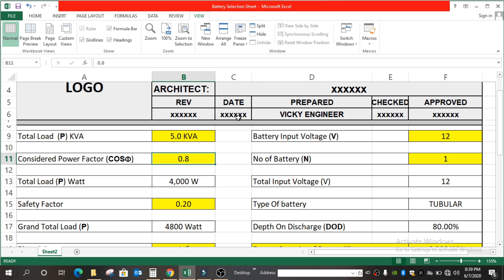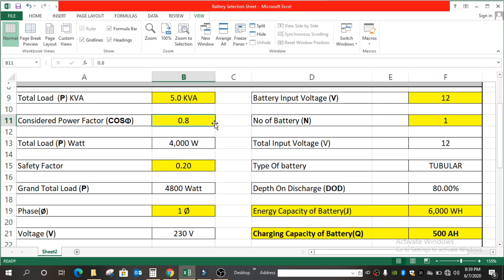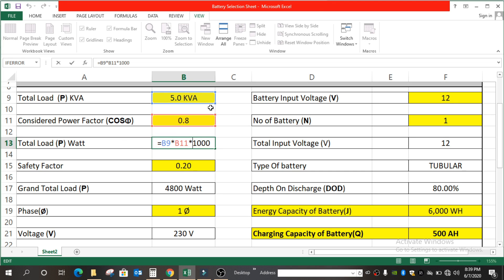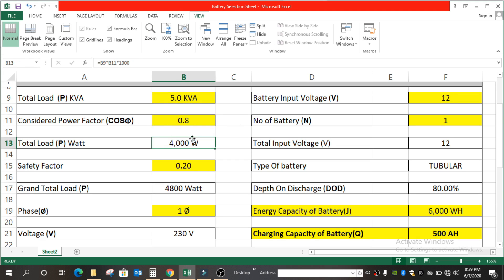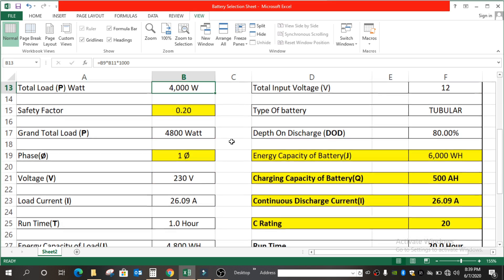The power factor — cos φ — we have considered as 0.8. If in your area it is different, you can always enter 0.5 or 0.9 as applicable. So we get 4,000 Watts as the total load. That is B9 (the KVA) multiplied by 0.8 (the power factor) multiplied by 1,000, giving us 4,000 Watts total load.